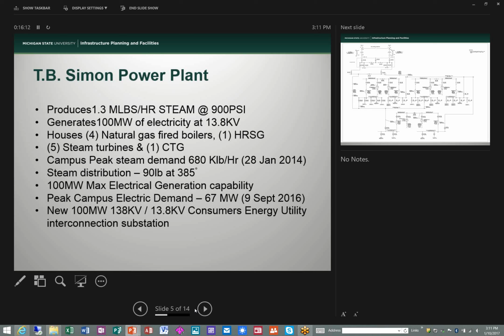This Christmas break, with kids just returned Monday, we were sending the campus about 380,000 pounds per hour to heat the buildings with nobody here. Electric demand was just under 40 megawatts with nobody here. So during winter break, the campus was still chewing up 40 megawatts and 400,000 pounds of thermal requirements while closed.